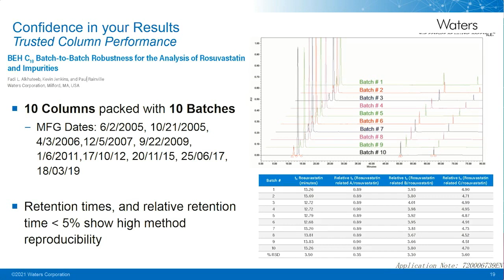The next part of our journey that we want to discuss is the best consumable for your system. What column configuration is best for your system needs to be considered because the fact is not all systems are created equally. There are many LC systems on the market, and most of these LCs are column agnostic when it comes to the analytical columns that you can attach to them. For older HPLC, the typical column is 4.6 millimeter in internal diameter, packed with greater than 3 micron particles. However, in recent years, as the column technology has improved, improvements to the system have also been made to realize the performance benefits of high-performance LC columns.